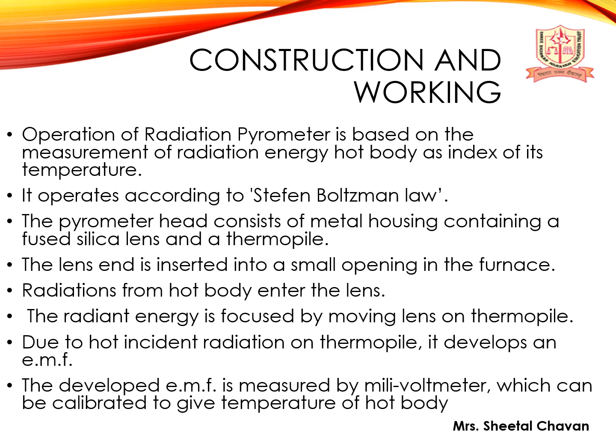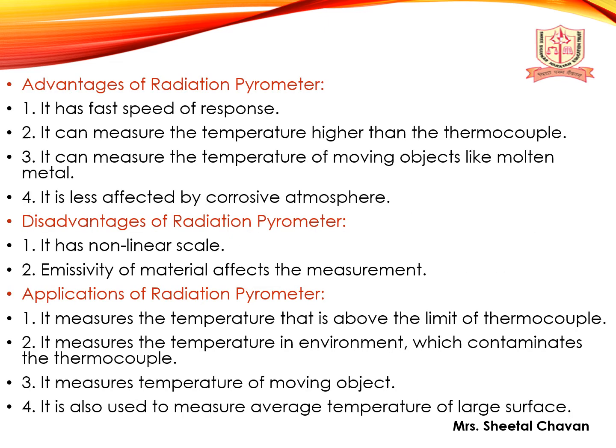Radiations from the hot body enter the lens. The radiant energy is focused by moving the lens onto the thermopile. Due to the incident radiation on the thermopile, it develops an EMF. The developed EMF is measured by the millivoltmeter, which can be calibrated to give the temperature of the hot body.